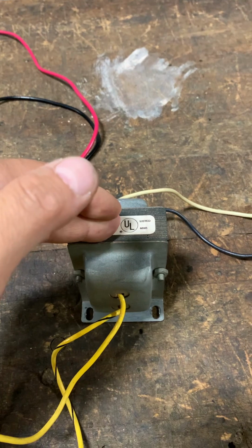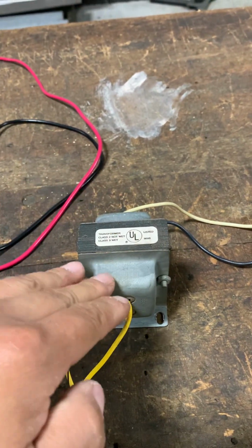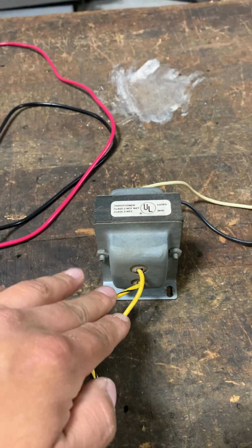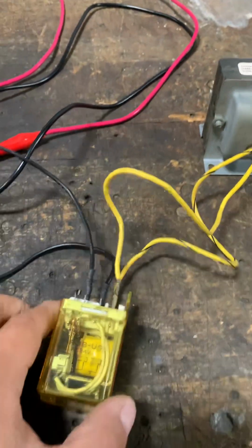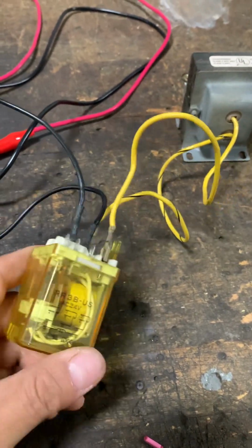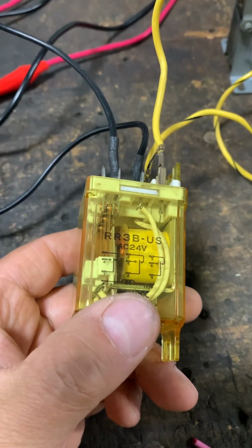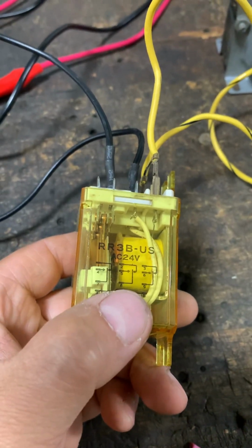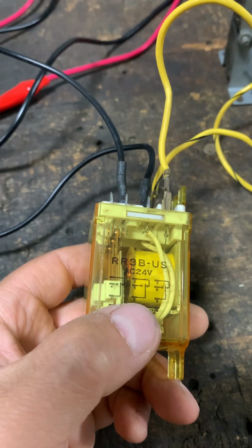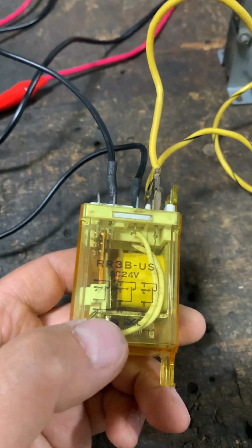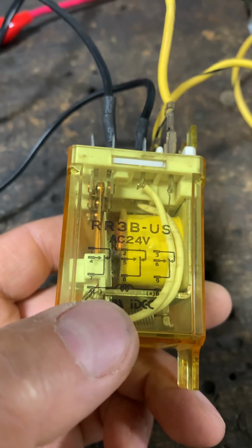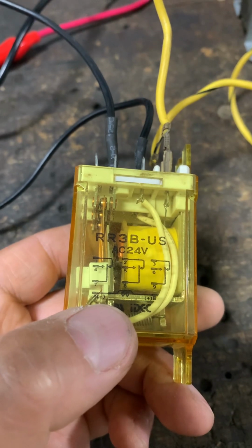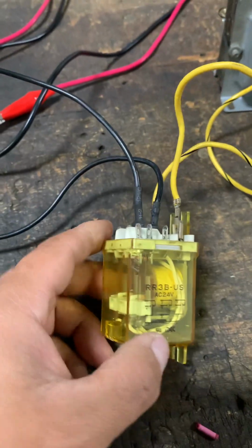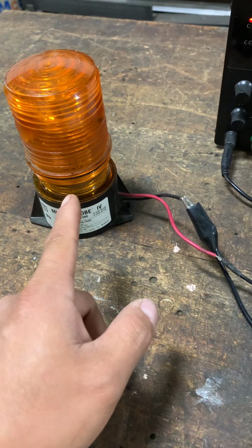Now we can use a 120, step it down to 24 volts AC. Now we can energize the coil on this relay. I have this relay wired to pins 8 and 5, which are normally open. Pins 8 and 2 are normally closed. So I have my load wired to pins 8 and 5 on the normally open side, which will then energize this light.